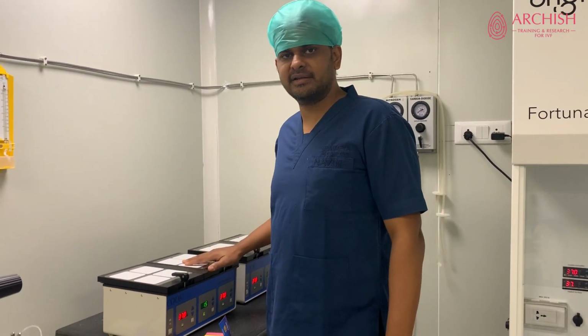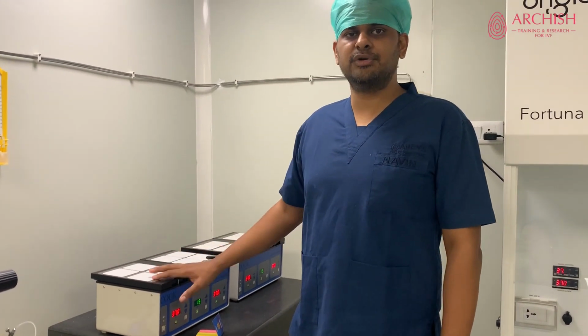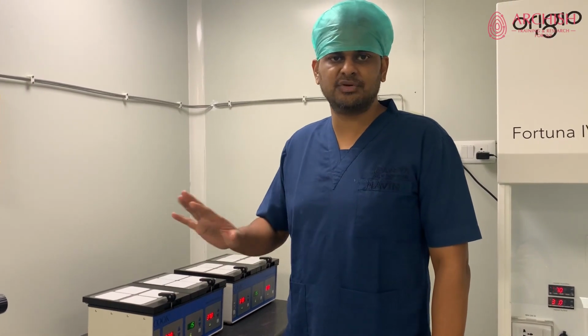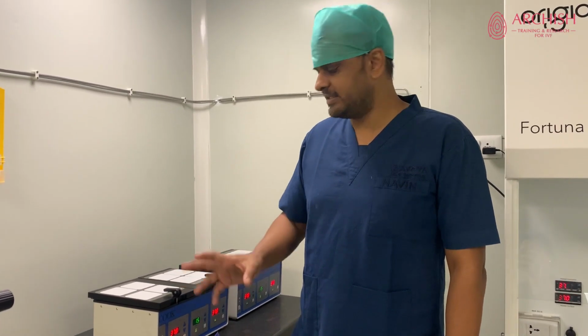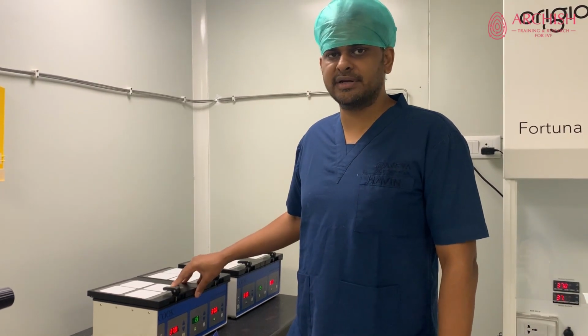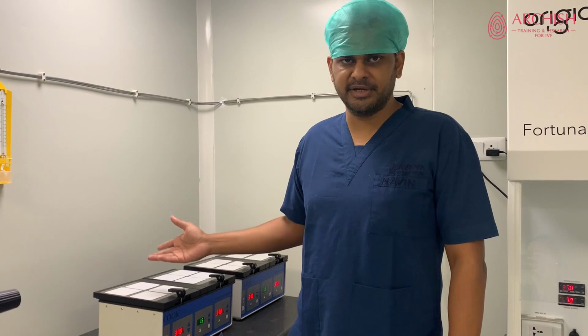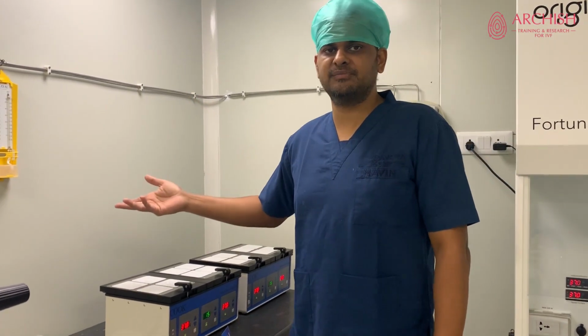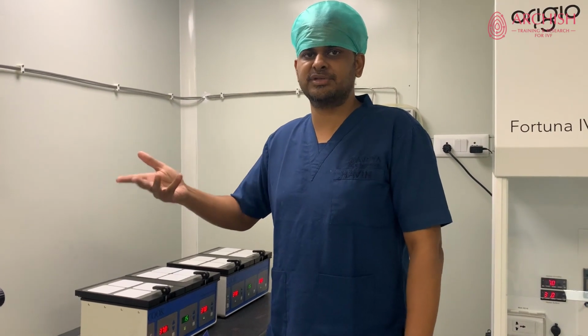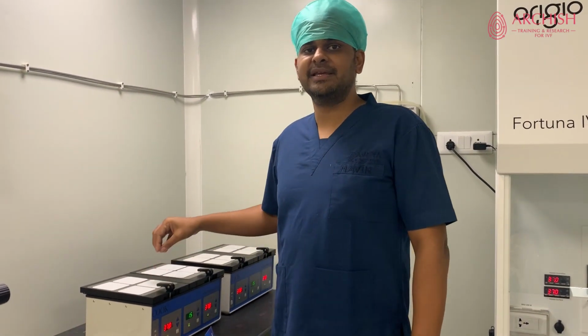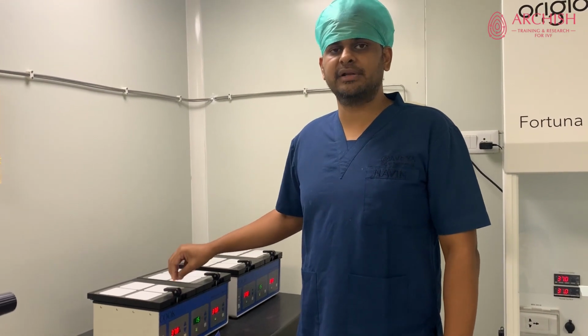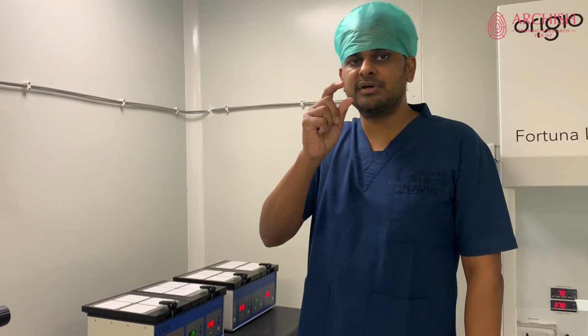Similarly, the other aspect you need to check in an incubator is not just temperature and CO2, but water content. Because if the water is out, then no matter if your temperature and CO2 are at the normal readings of 37 degrees plus or minus 0.5 degrees, being out of water is going to kill your embryos or stop their development. For example, if you're looking for a day 3 to day 5 move, you might be wondering why the day 3 embryos are not progressing to blastocyst. That could be a very key finding, or a critical factor in analyzing why that particular switch might not happen, if you leave aside the clinical parameters or the individual egg and sperm parameters.